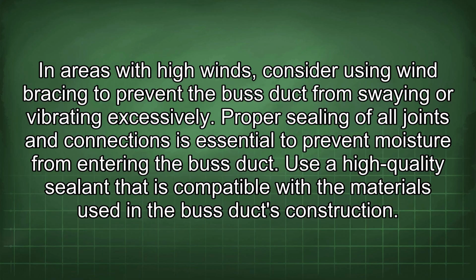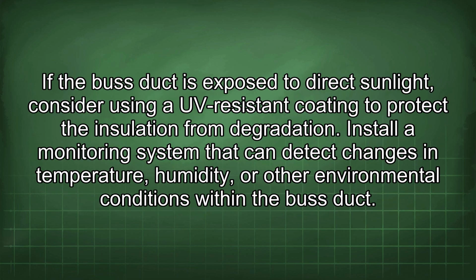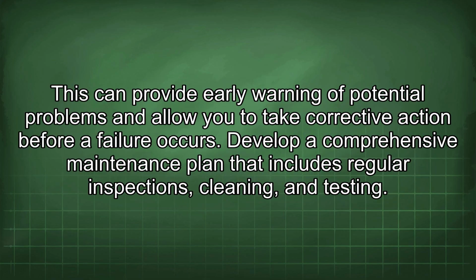Proper sealing of all joints and connections is essential to prevent moisture from entering the bus duct. Use a high-quality sealant that is compatible with the materials used in a bus duct's construction. If the bus duct is exposed to direct sunlight, consider using a UV-resistant coating to protect the insulation from degradation. Install a monitoring system that can detect changes in temperature, humidity, or other environmental conditions within the bus duct. This can provide early warning of potential problems and allow you to take corrective action before failure occurs.